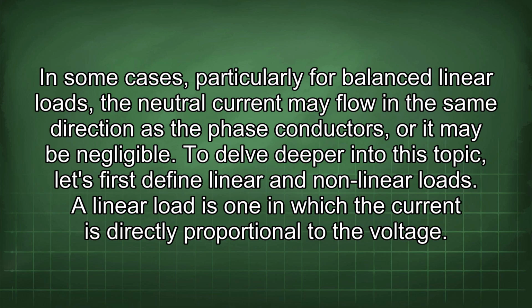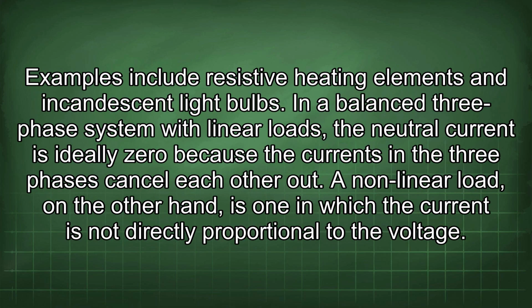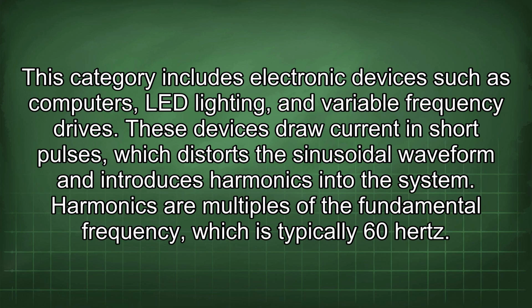To delve deeper into this topic, let's first define linear and nonlinear loads. A linear load is one in which the current is directly proportional to the voltage. Examples include resistive heating elements and incandescent light bulbs. In a balanced three-phase system with linear loads, the neutral current is ideally zero because the currents in the three phases cancel each other out. A nonlinear load, on the other hand, is one in which the current is not directly proportional to the voltage. This category includes electronic devices such as computers, LED lighting, and variable frequency drives. These devices draw current in short pulses, which distorts the sinusoidal waveform and introduces harmonics into the system.